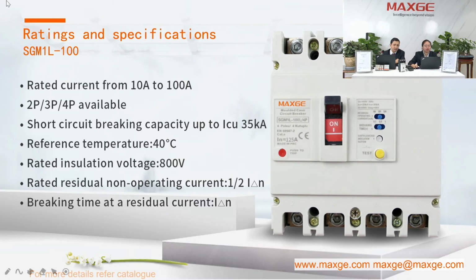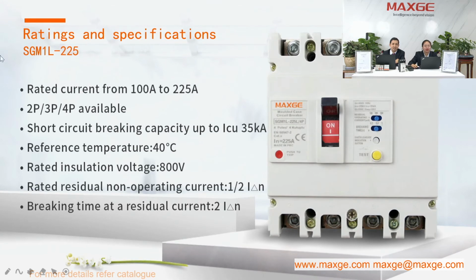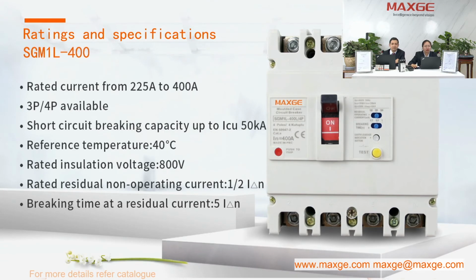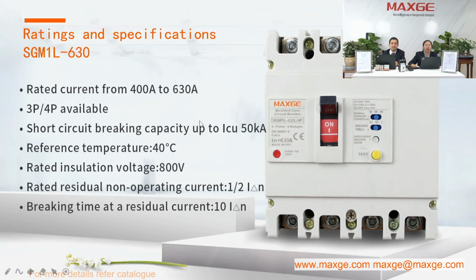Earth leakage protection. So for the 100 ampere frame size, we have 2-pole, 3-pole, 4-pole available, and the rated current from 10 to 100 ampere. And for the 225 frame, we also have 2-pole, 3-pole, 4-pole. And 400 frame, we have 3-pole and 4-pole, rated current from 225 to 400 ampere. 630 ampere frame, rated current from 400 to 630 ampere, and 3-pole and 4-pole available. The breaking capacity can go up to Icu 50 kA.